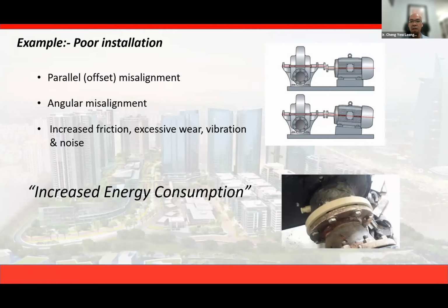You have a chill water pump when you install a condenser water pump. If the pump and motor alignment is not in line, you will have problems. What are the problems? You will increase friction loss, excessive wear and tear, vibration and noise issue. So the motor has to drive harder, meaning you increase energy consumption. So what's the point of having a high efficiency motor if the pump is not installed properly? Correct.